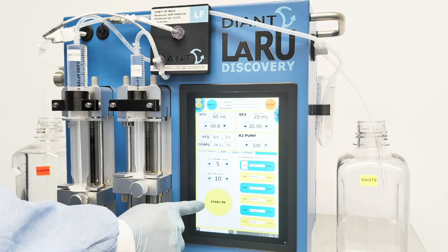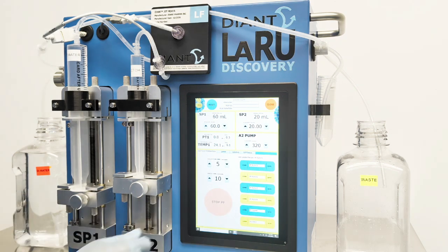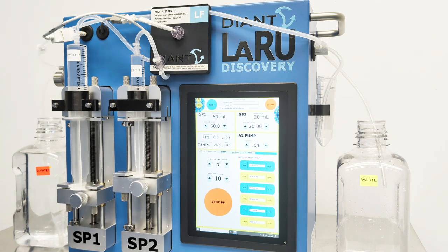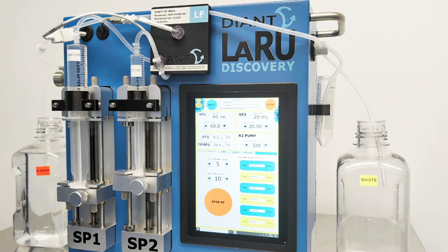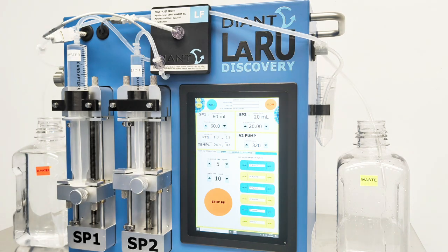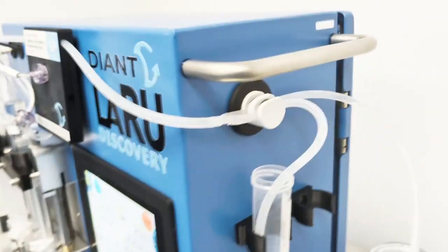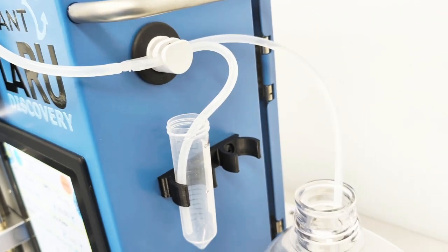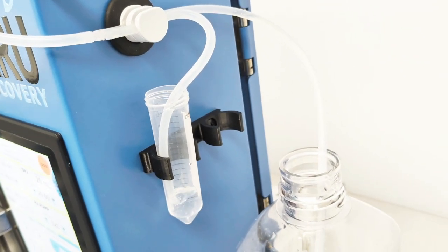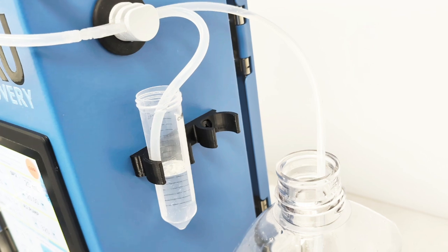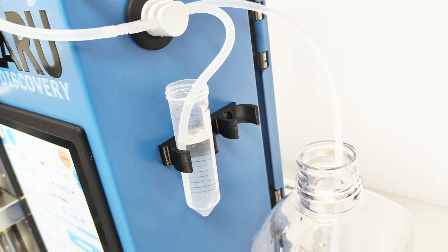Once you're ready, click Start PF. The initial waste time is set for 10 seconds. As you can see, the liquid begins to flow. And then the valve clicks over, and we start collecting our sample for 5 seconds. And that's it. You've made your first particles.